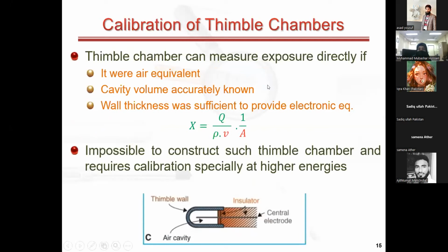However, these thimble chambers require calibration. Let me tell you that these thimble chambers can measure exposure directly as well without requiring any calibration, only if, first, it is really air equivalent. Second condition is that the cavity volume is accurately known. And the third condition is that the wall thickness of this thimble chamber is sufficient to provide electronic equilibrium.